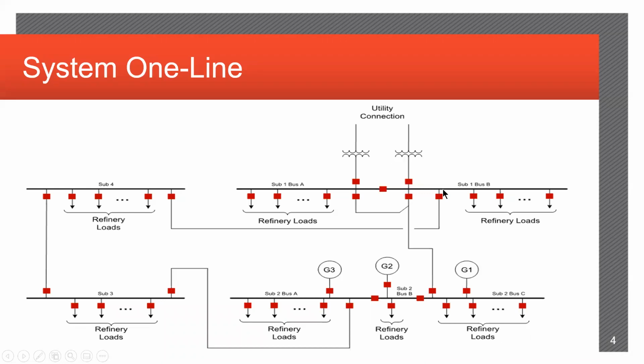PDC. What is not shown on here, and I really hadn't intended to present on, is that there is actually a load shedding scheme in place at the refinery, and anytime that this connection to the utility is lost, they intentionally dump a bunch of non critical loads up here at this main PDC.